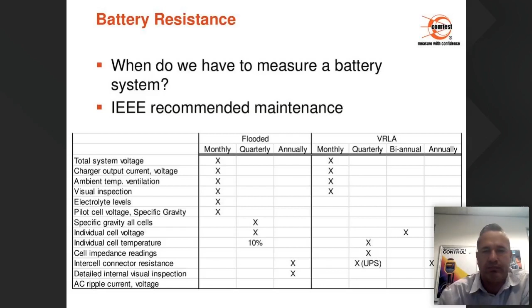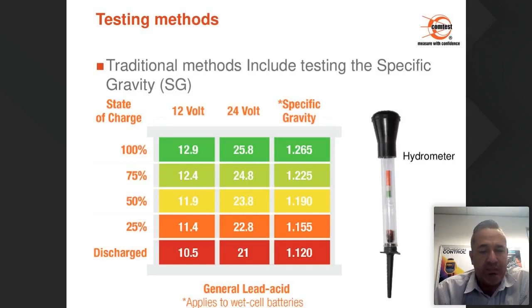So our traditional method of testing your flooded lead acid batteries is by using specific gravity tests. This involves using the hydrometer that you can see in the image on the right hand side. This little pipette you would push into the cells, and then you would test each cell for the charge state, based on a little floater inside the hydrometer telling us what the charge level is. So this is how traditionally we used to test the batteries.